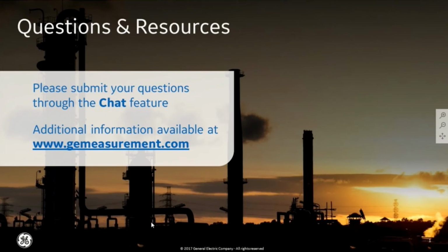That's something that we can consider for future development, future releases, but so far we haven't encountered a demand for that yet. Now, just to add to that, we certainly can block the app by password for any modifications, but as far as, if someone has access to the instrument and the app is loaded on there, then they would be able to run it.